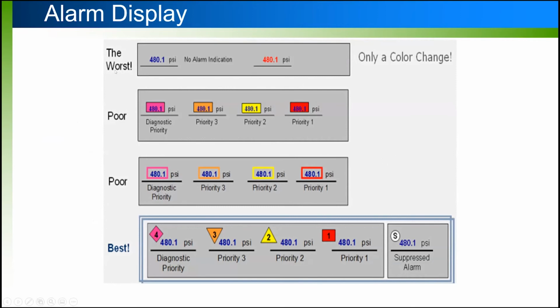One thing you don't want to do is change the color of the text when there's an alarm, don't change it from blue to red just because it's in alarm state. I've come across screens where the text changed color, but the equipment behind it was a similar color, so you couldn't really read the text. That was just a bad practice. Instead, leave the value alone, it stays the same color, it doesn't move around, it doesn't flash, but you display the alarm status next to it.